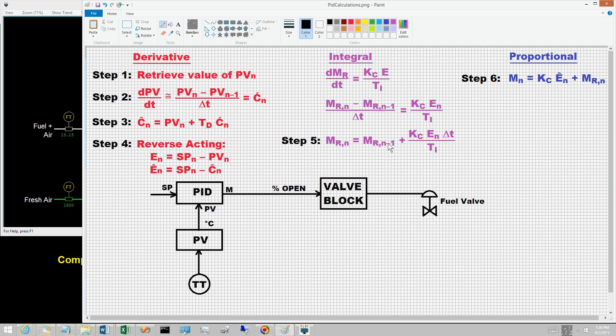The initial condition is the value m sub r 0 computed for bumpless transfer. For the integral mode calculations, the finite difference approximation is acceptable — there seems to be no incentive to use better numerical approximations to compute the integral. A subsequent video explains an alternate implementation known as reset feedback for the integral mode, where the calculations are based on the controller output m instead of the control error e. Another video examines integrating the projected control error e-hat instead of the current error e, resulting in a PID equation slightly different from those previously presented.